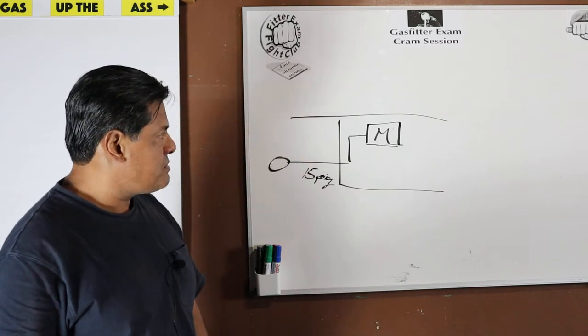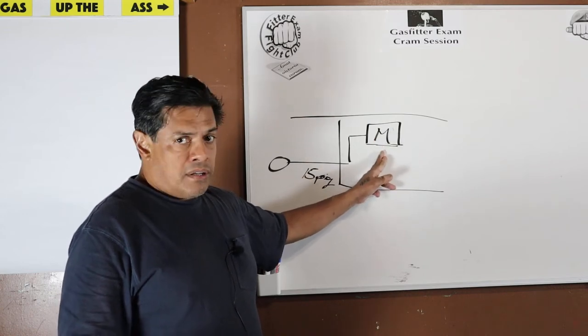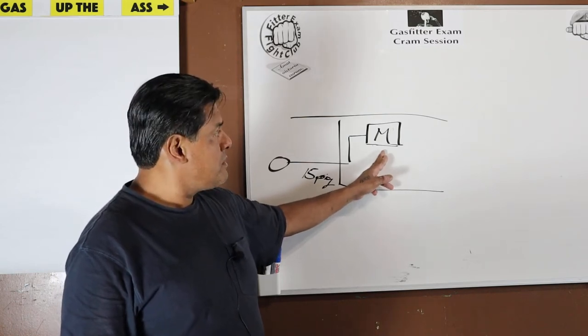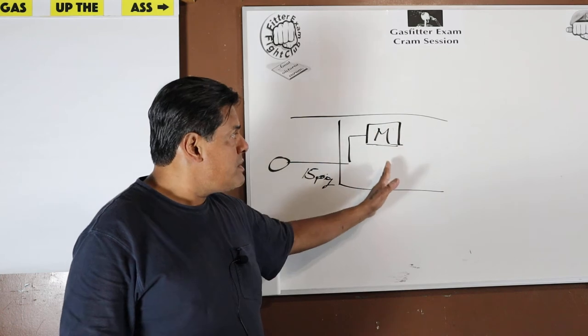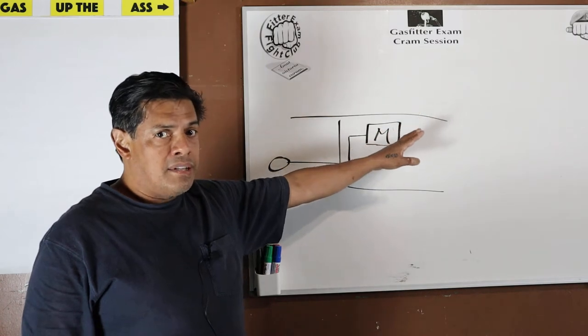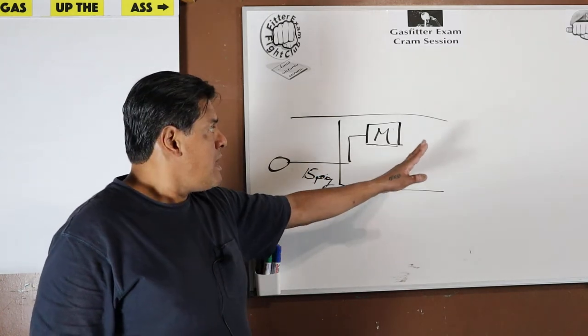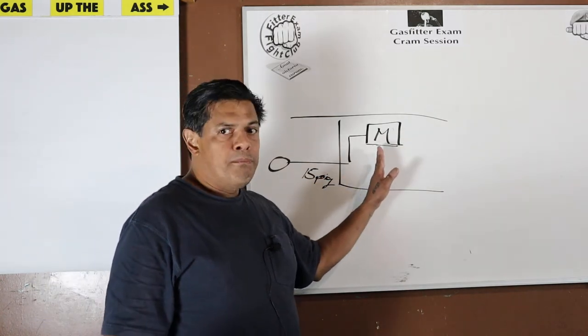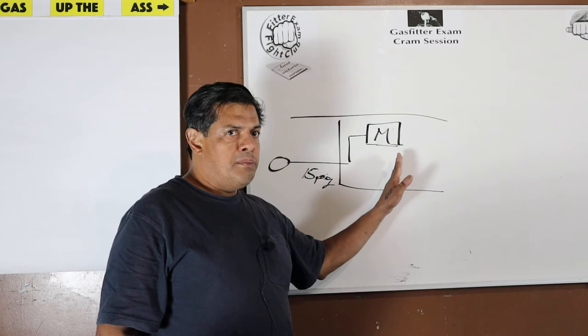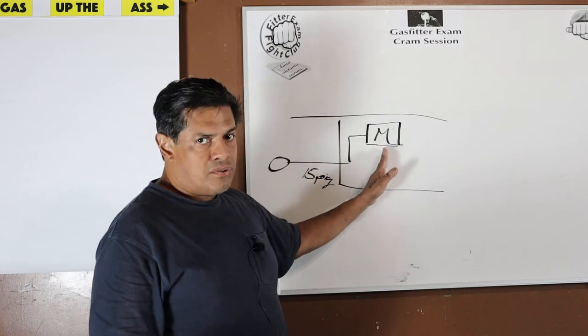So we've got high pressure gas in the street. It's coming in here. It's going to go to the meter. This meter is designed to deal with half a PSI. This meter, I'm going to say, is strictly for cooking gas. It's measuring the amount of gas all the stoves in the building are using. And they're using it at least half a PSI, more likely, as we mentioned before, a quarter PSI. But still, you can't go from 15 PSI to a meter, a delicate, calibrated instrument that's only meant to deal with poundages of a half. The 15 is going to destroy this meter.